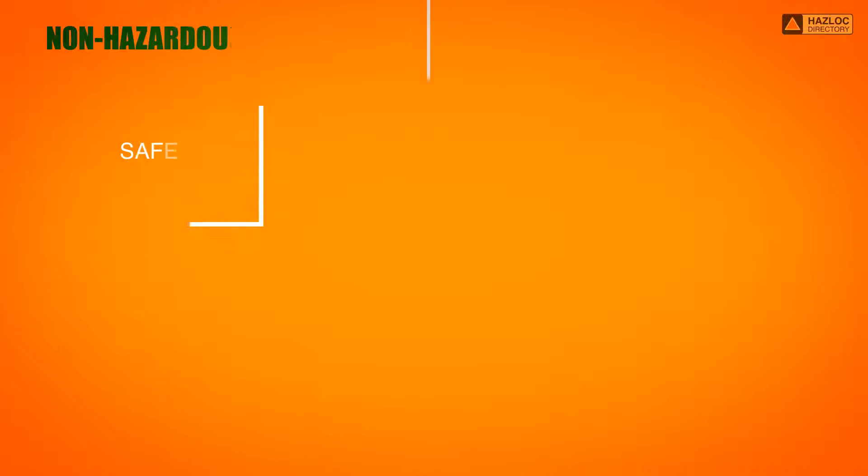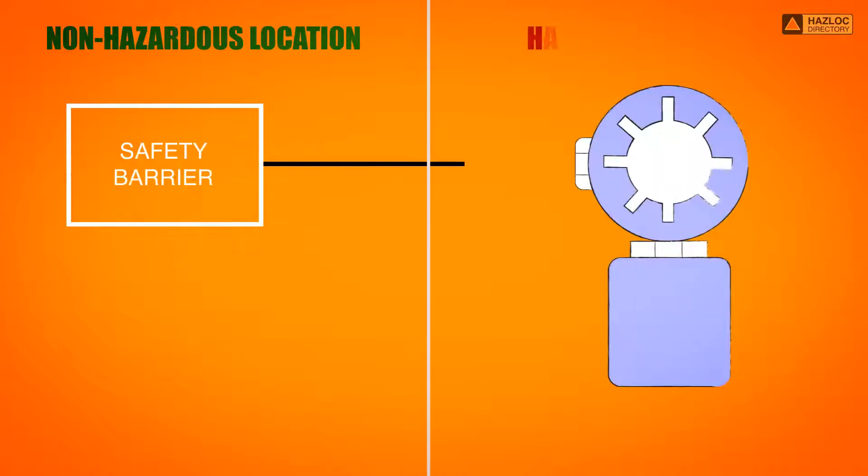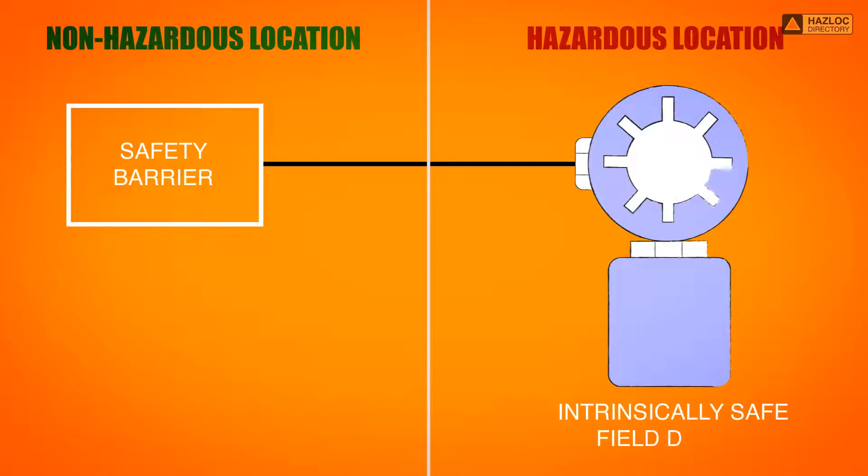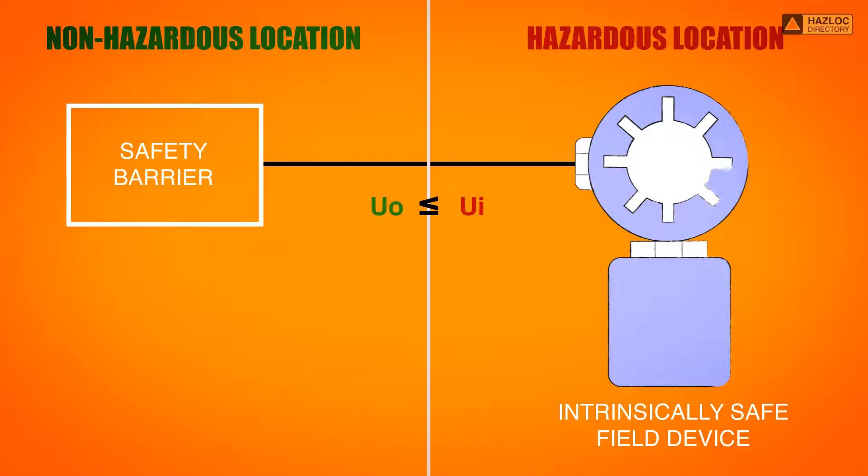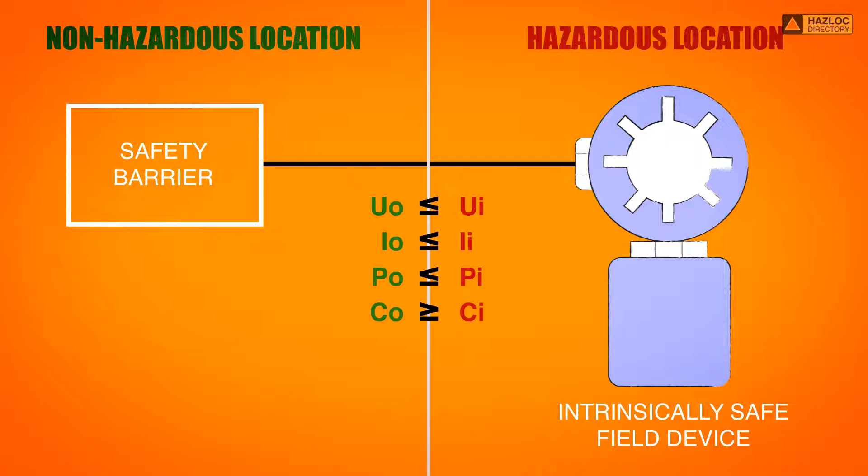In order to select a safety barrier that would make a safe connection that complies with the entity parameters concept, we need to ensure that the input voltage of the IS field device is greater than or equal to the output voltage of the safety barrier. The same relationship is true for current and power. The maximum equivalent internal capacitance of the intrinsically safe device must be less than or equal to the maximum allowed capacitance of the connected safety barrier. The same is true of the inductance value.